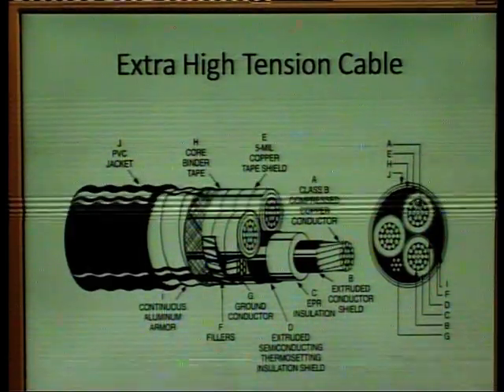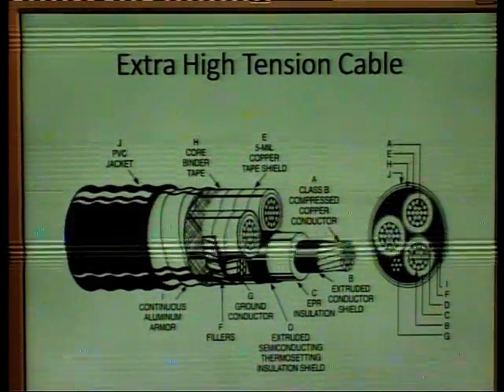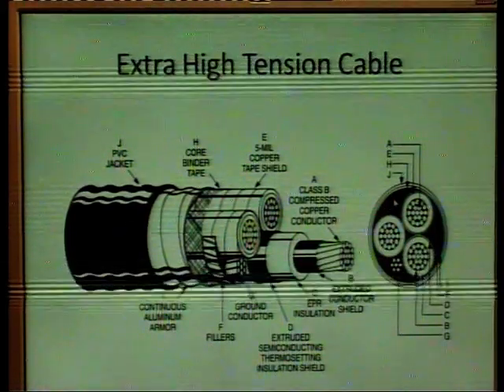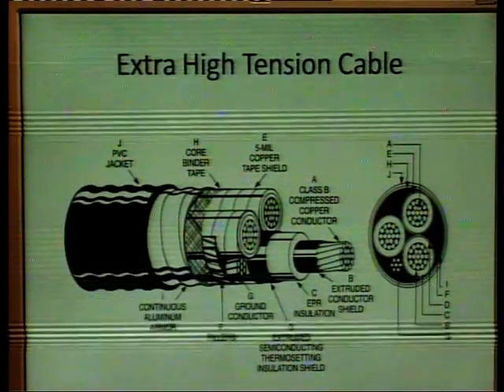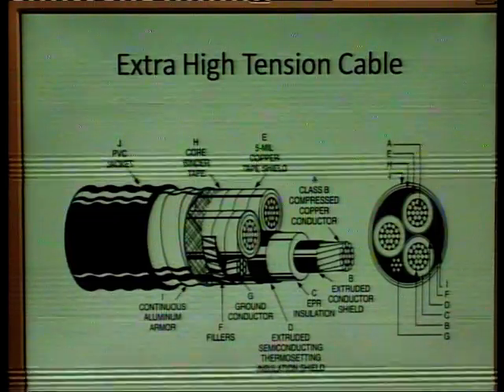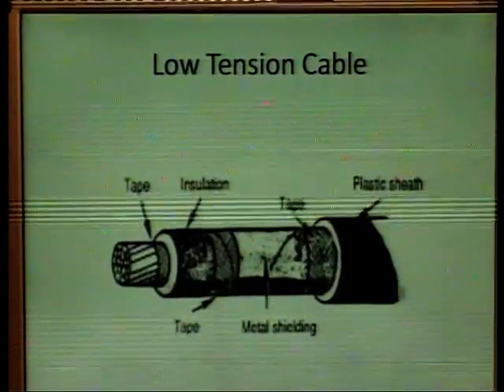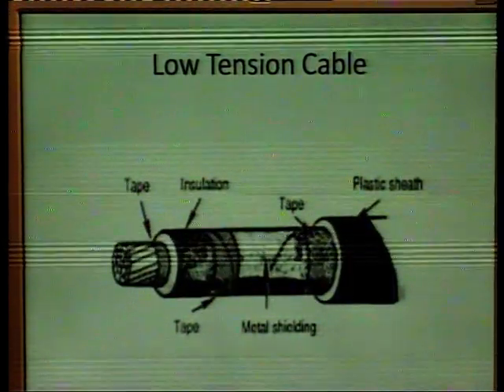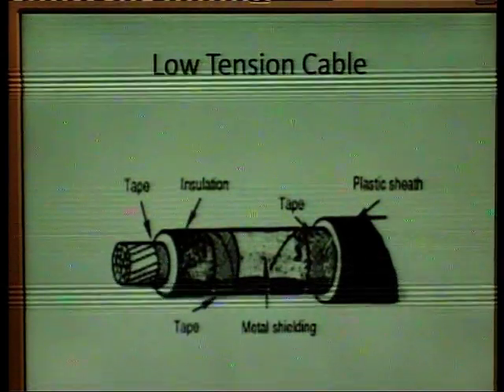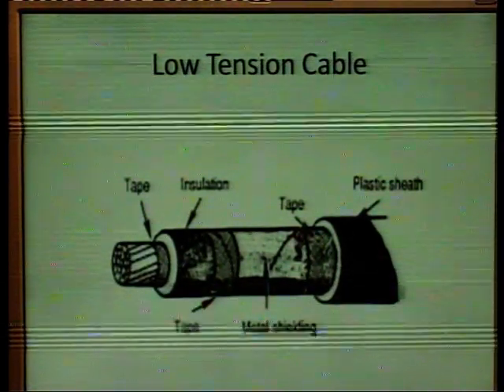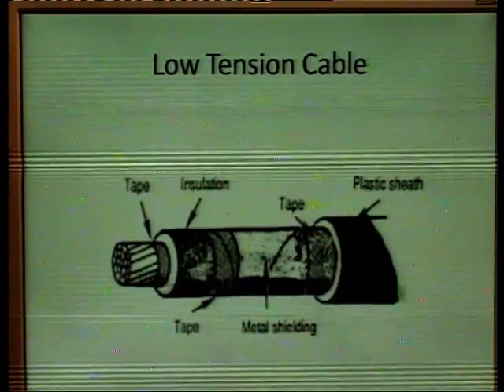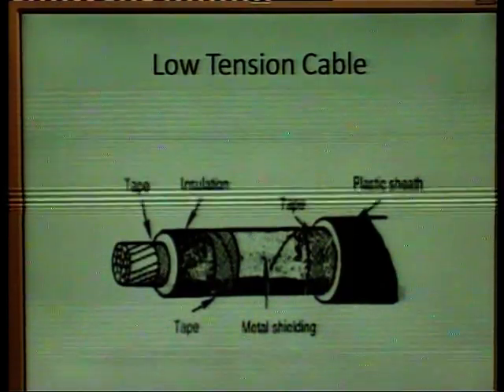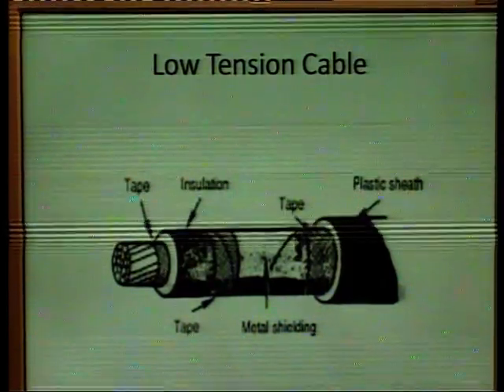You can also see the side view of the EHT cable. And this is the LT cable, low tension cable. Plastic sheath is there, tape, metal shielding, tape, insulation, then again tape, then the conductor.